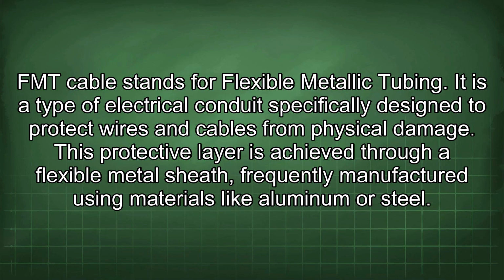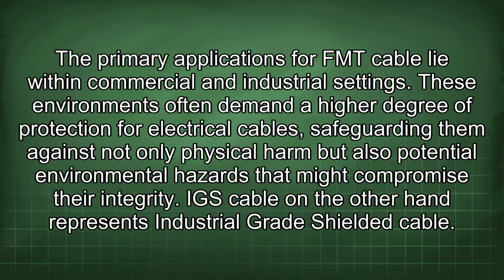FMT cable stands for flexible metallic tubing. It is a type of electrical conduit specifically designed to protect wires and cables from physical damage. This protective layer is achieved through a flexible metal sheath, frequently manufactured using materials like aluminum or steel. The primary applications for FMT cable lie within commercial and industrial settings. These environments often demand a high degree of protection for electrical cables, safeguarding them against not only physical harm but also potential environmental hazards that might compromise their integrity.